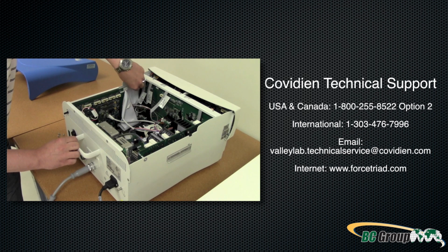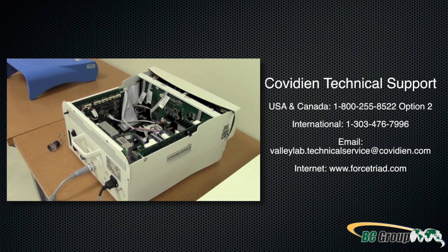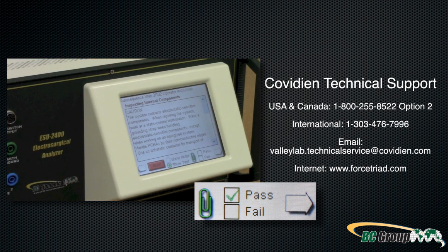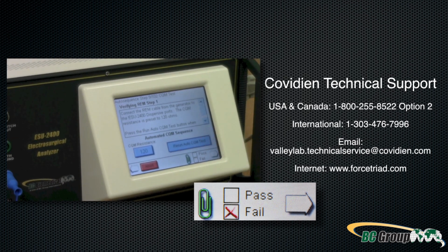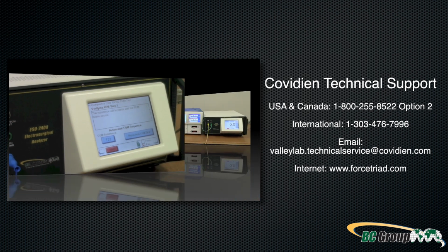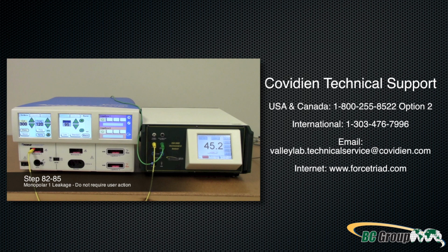General information. Each step in this video corresponds to a step of the Autosequence as detailed by the ESU-2400. At the end of each step, you should review all of the instructions displayed on the ESU-2400. If the device under test passes, then check the box next to Pass and touch the arrow on the bottom right of the screen to advance to the next step of the Autosequence. Should you experience a fail condition, you should verify the connection specified by the step and repeat. If the device under test cannot pass the step, you should contact Covidien Technical Support. Throughout this video, some steps will be described as not requiring user action. During these steps, the ESU-2400 is running automated tests, communicating with the ForceTriad, and triggering events to collect data, dramatically reducing the time required to complete the PM.